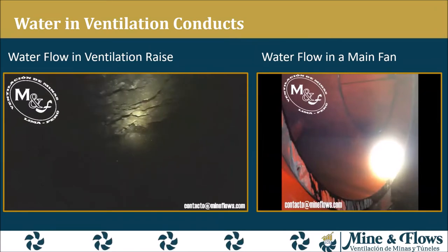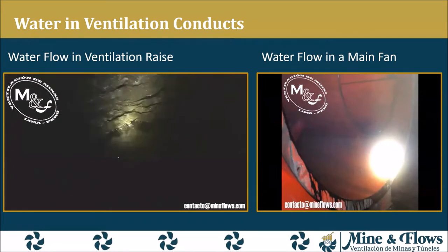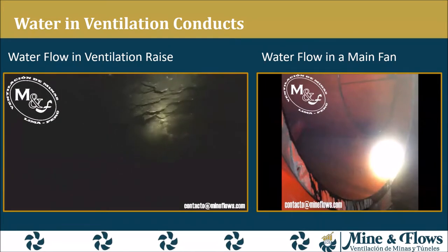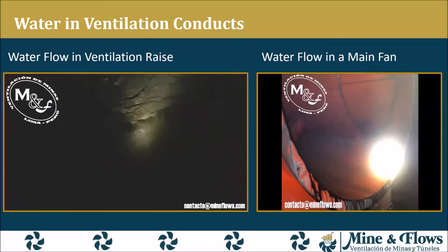The presence of water filtration in underground mines is very common, especially in exhaust ventilation branches, like ventilation raises, because these have a negative pressure generated by exhaust fans, like a straw to drink water. This induced water flow can complicate the system because for certain air velocity, the water can float in the air, increasing the resistance of the system.